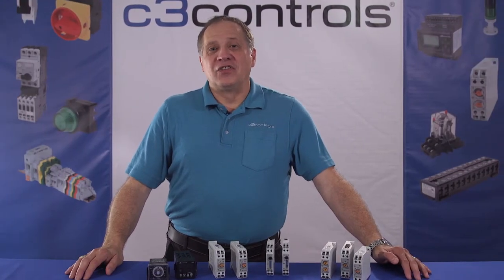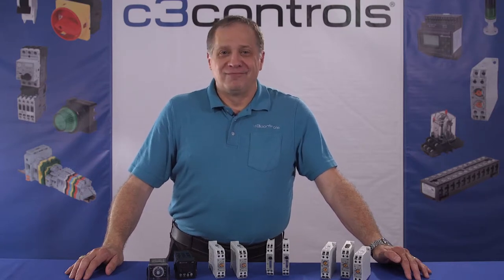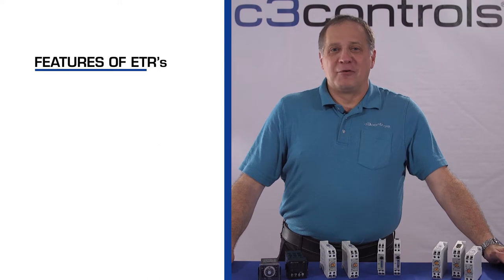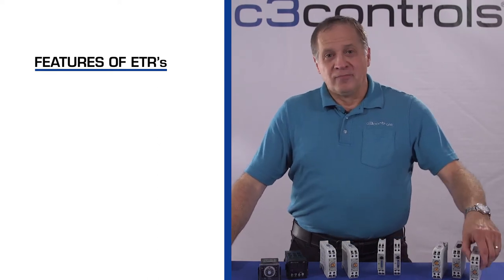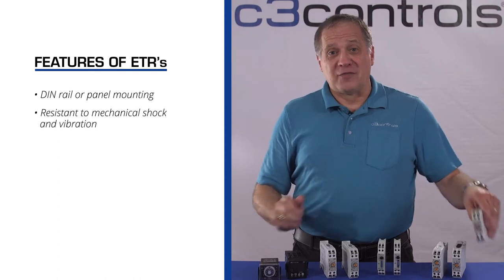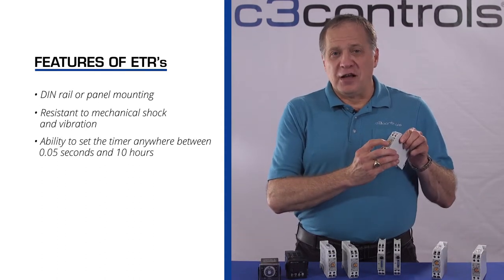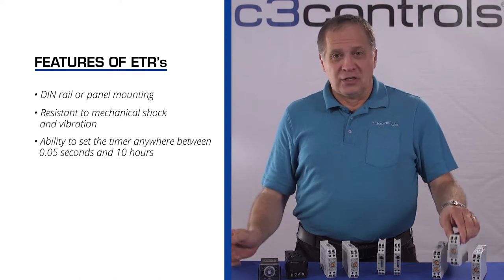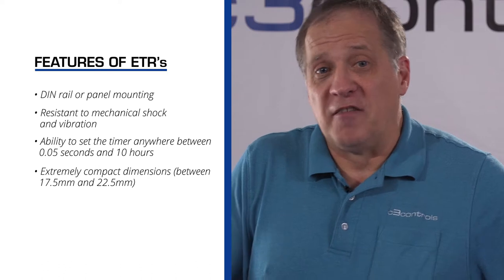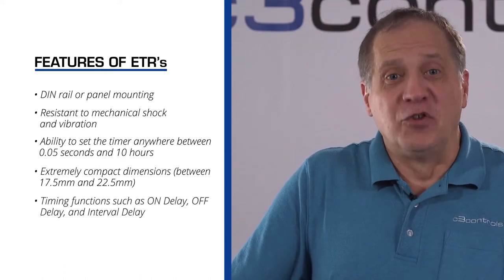ETRs provide a wide range of selectable functions so that users can customize their specific machine operation. Features to look for in electronic timing relays include DIN rail or panel mounting, resistance to mechanical shock and vibration, the ability to set the timer anywhere between 0.05 seconds and 10 hours, extremely compact dimensions between 17.5 and 22.5 millimeters, and timing functions such as on delay, off delay, and interval delay.